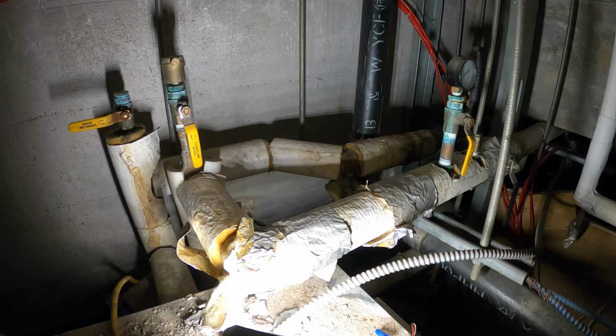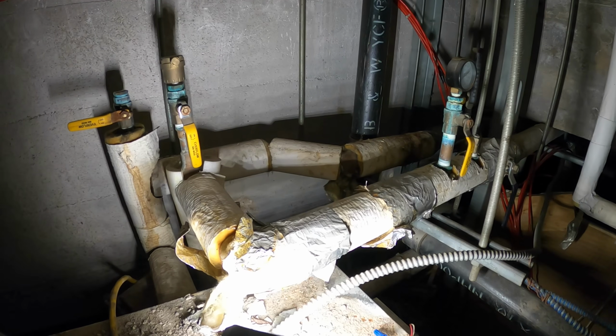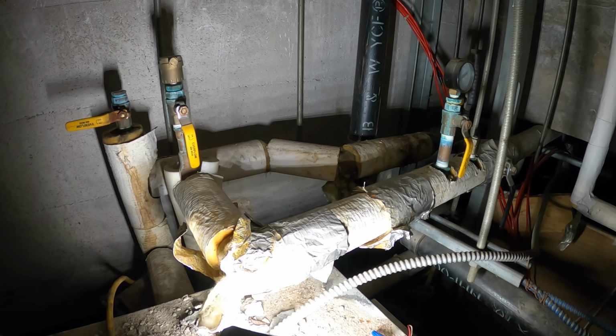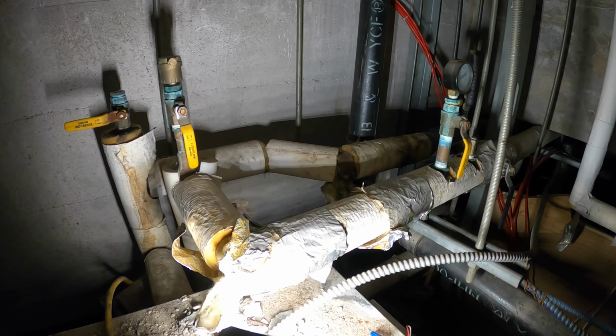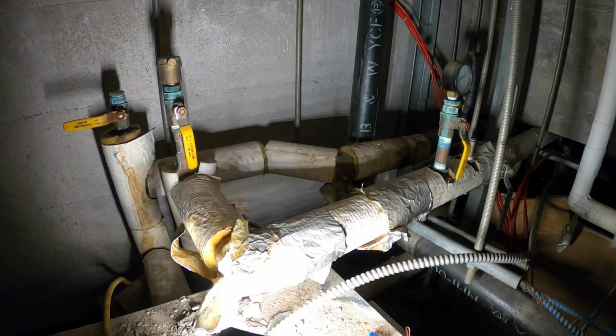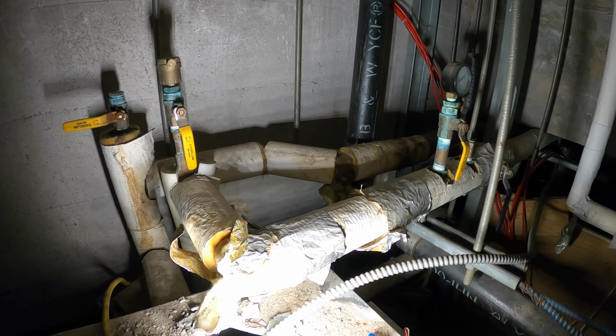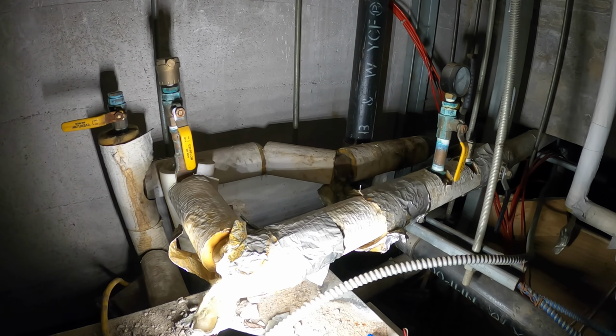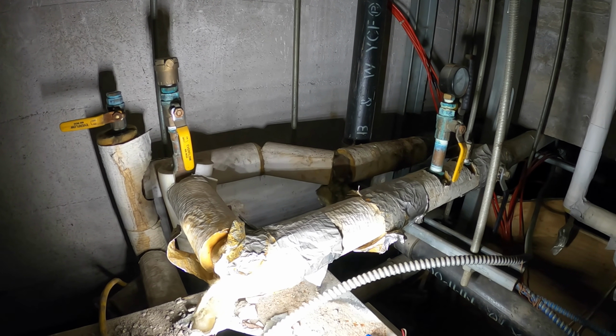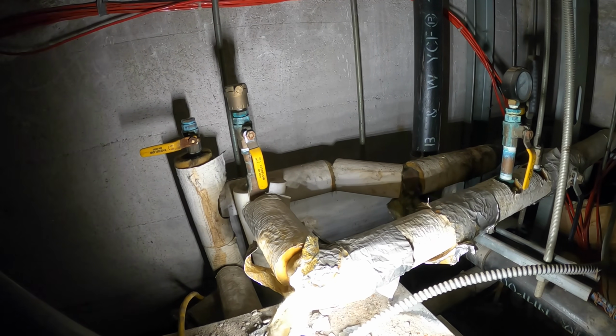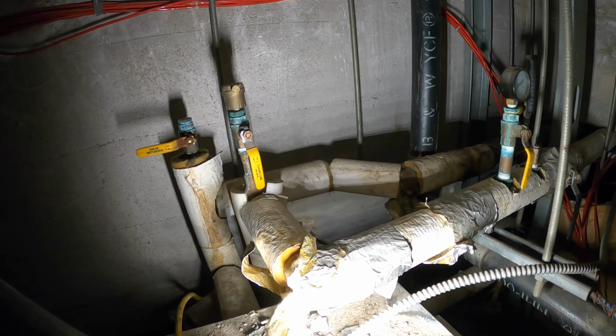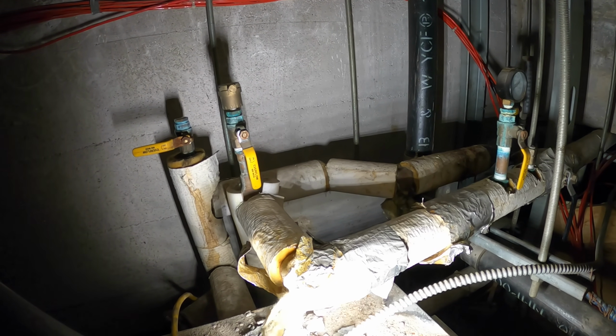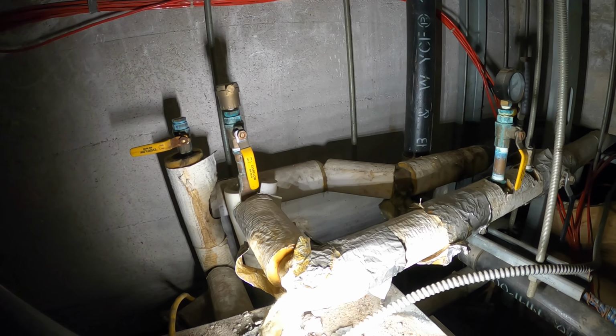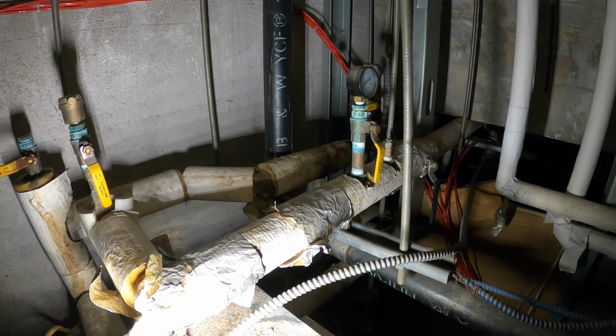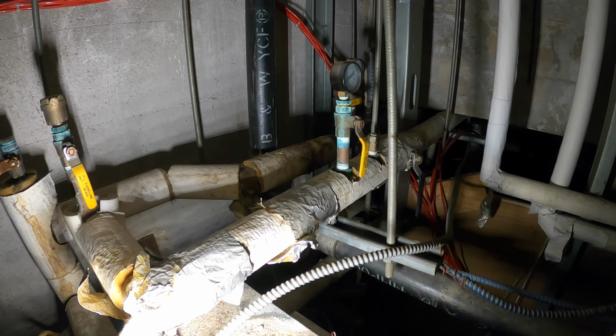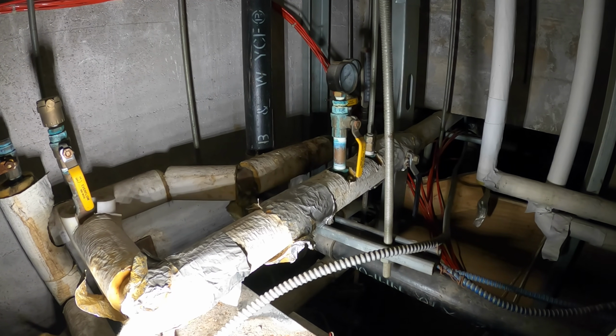We gotta also, you know what? We gotta make sure that the chiller is on. But I'm sure they would have called me if they had a problem with no cooling anywhere. All right, so heating and cooling actuator both open and close. Bypass is open for the chilled water, so we're 100% moving water. Still doesn't get cold. We closed the hot water valves manually to make sure we're not squeezing by.